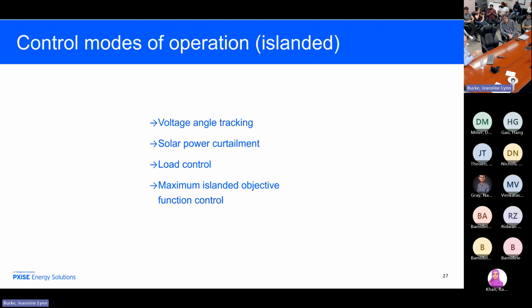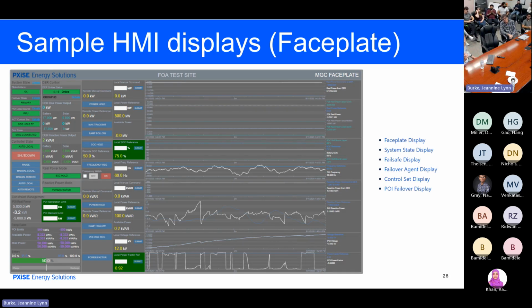I've mentioned frequency control and so forth. I'm not going to go through this because it looks extremely complicated. It sort of is extremely complicated, but every DCS system I've worked with in the past years has a faceplate. And a faceplate shows you the set point, the value, and the status: is it auto, manual, remote or control.